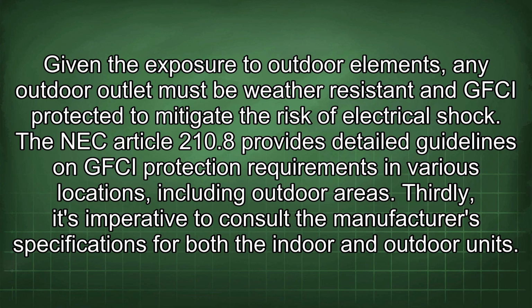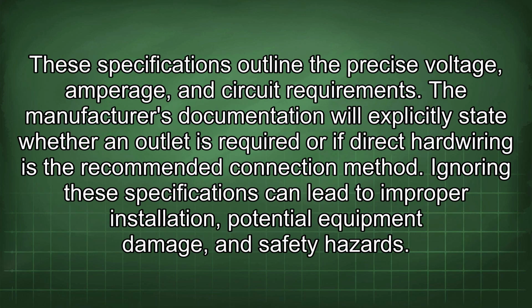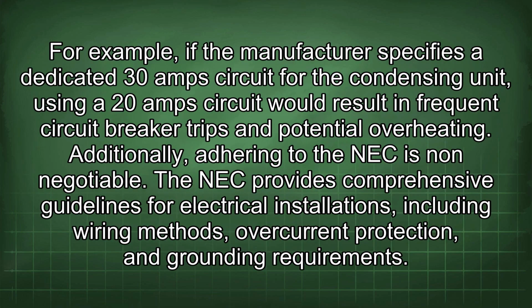Thirdly, it's imperative to consult the manufacturer's specifications for both the indoor and outdoor units. These specifications outline the precise voltage, amperage, and circuit requirements. The manufacturer's documentation will explicitly state whether an outlet is required or if direct hardwiring is the recommended connection method. Ignoring these specifications can lead to improper installation, potential equipment damage, and safety hazards. For example, if the manufacturer specifies a dedicated 30 amp circuit for the condensing unit, using a 20 amp circuit would result in frequent circuit breaker trips and potential overheating.